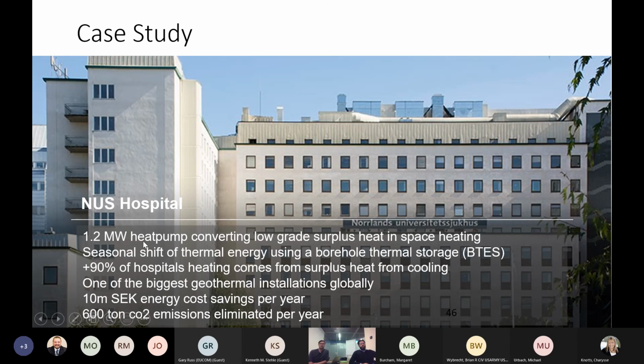They installed one of our heat pumps, a 1.2 megawatt system, basically in order to take advantage of all the surplus heat from their cooling systems. A hospital has a lot of medical equipment that needs constant cooling, and of course it's also operated 24/7. So they had a lot of surplus heat that they used to blow away on the roof with fan coils, and they wanted to see if they could use that for heating the hospital instead.